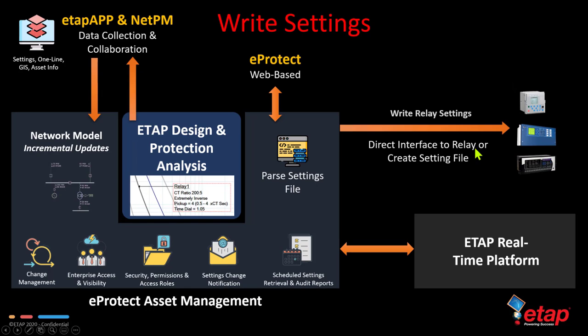And then it is also possible to essentially create that setting file that you can put onto a laptop and upload to a relay, or use the relay software to update the relay settings, or even have a direct interface to the relay and write the settings for the relays that actually support this type of communication. So through a complete automated process, eProtect can read and write settings, including creating the setting files, without having to redo or rewrite any of that information again.